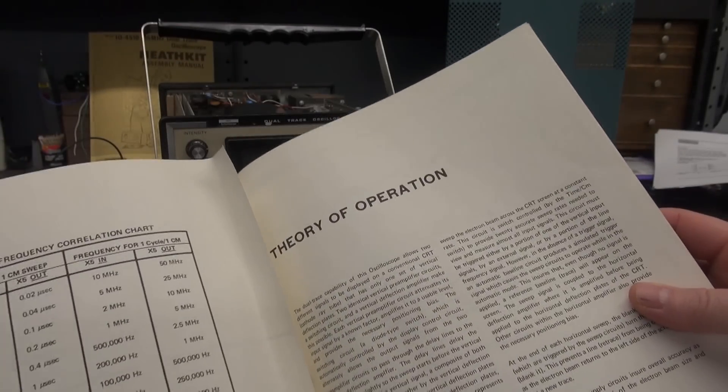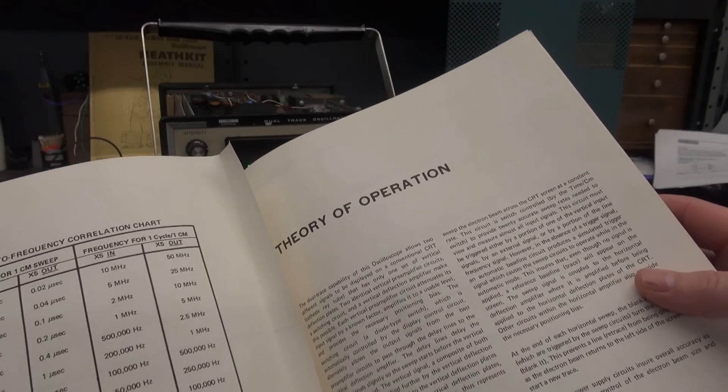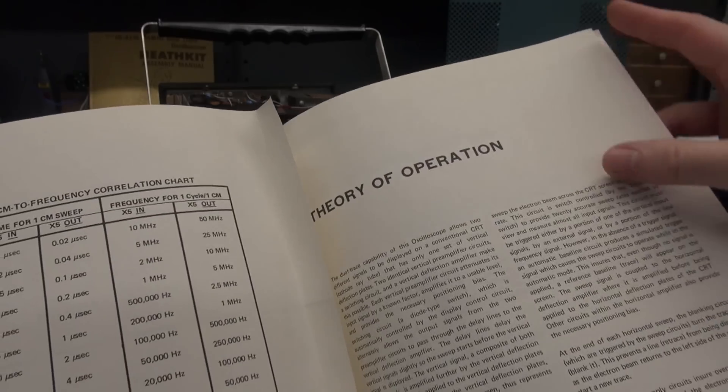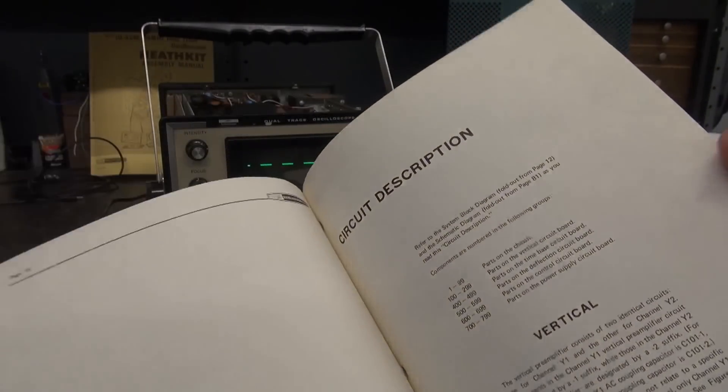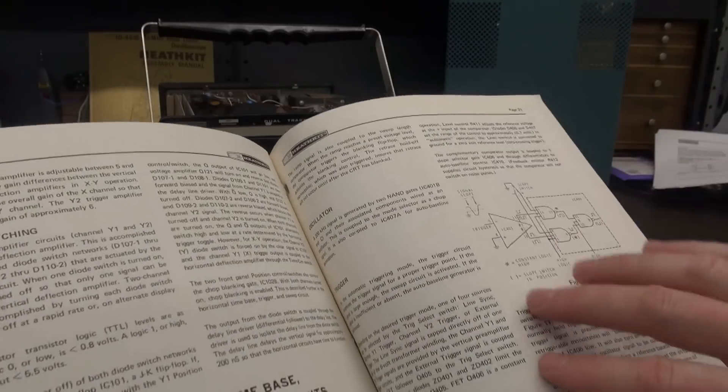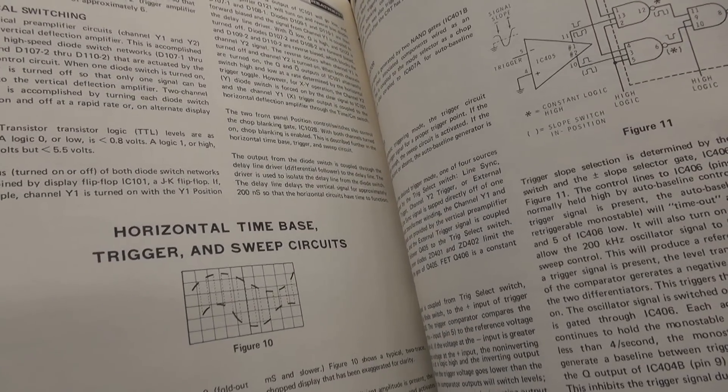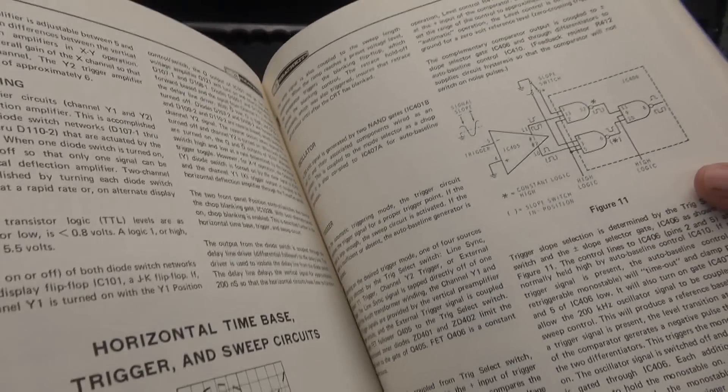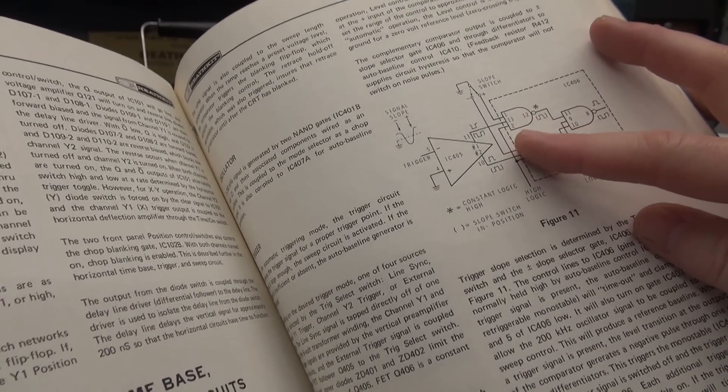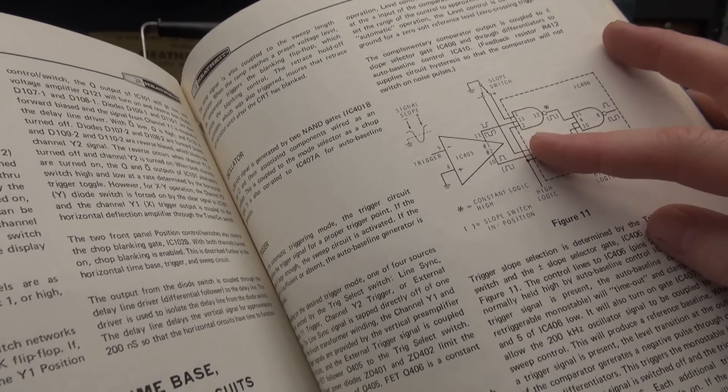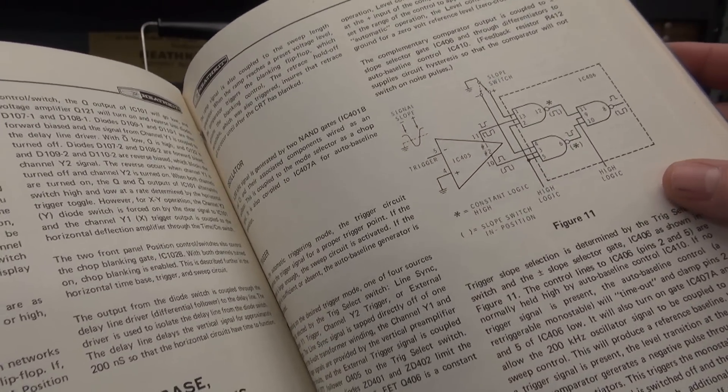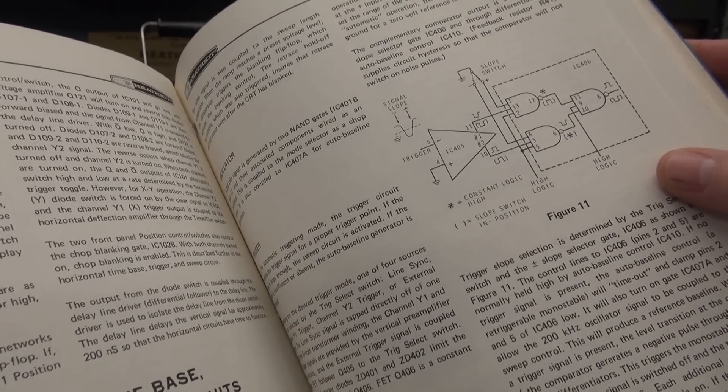Obviously the first thing you really want to do is get familiar with the circuitry. So I always read through the theory of operation, especially for the area that I'm concerned with. And if you flip through here, you will find the horizontal and triggering circuit description. So you want to read this very carefully, especially when they're talking about IC405, because guess what its job is? Yeah, that's the triggering chip. So where's the first place to go? IC405.